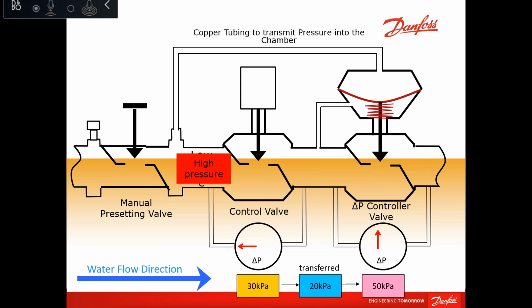Okay, and we have a question about the minimum flow setting. If the flow rate is 20% of the flow rate, is it okay to select this valve considering a 20% presetting? Based on how we set or test the valve in the factory, if we say 20% minimum is recommended, we can achieve that. But our testing rig is not the project. After time of operation, with the project at 20%, there might be a lot of things that will affect it.